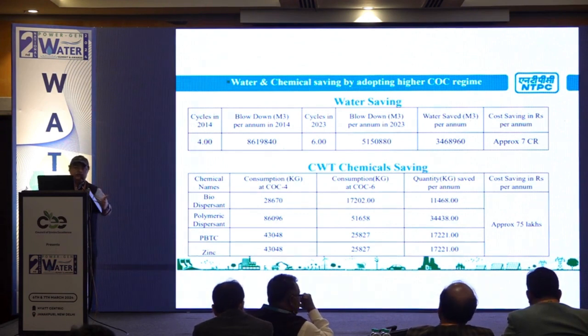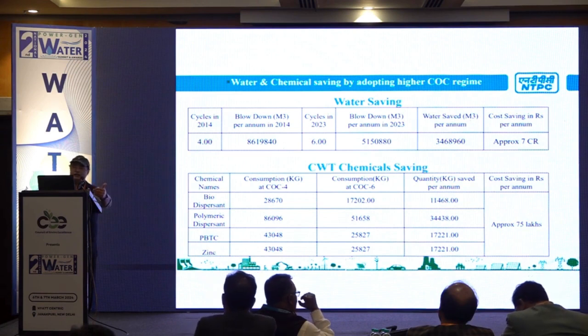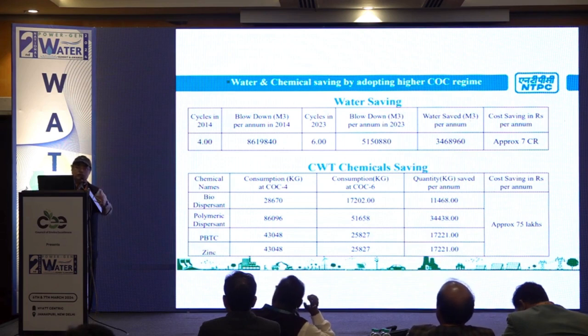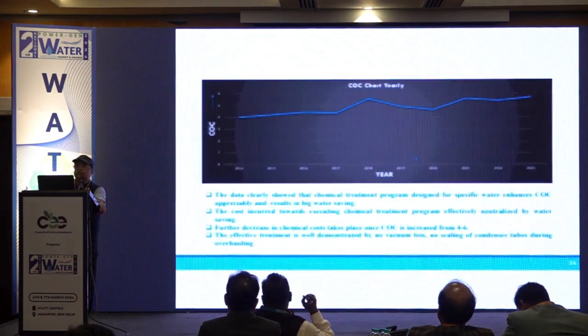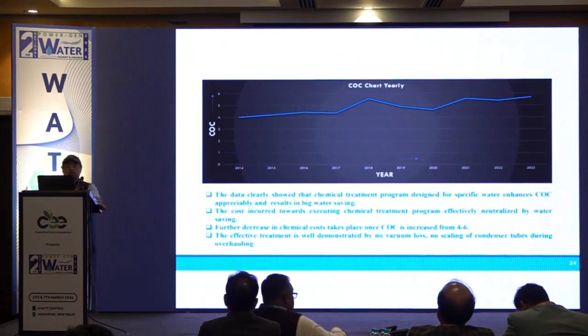Also, whenever COC is increased from 4 to 6, the cost of chemicals decreases, because we use lesser chemical now as blowdown is less, and to treat the fresh or raw makeup we need lesser chemicals. So there is some additional saving of 75 lakhs from that.